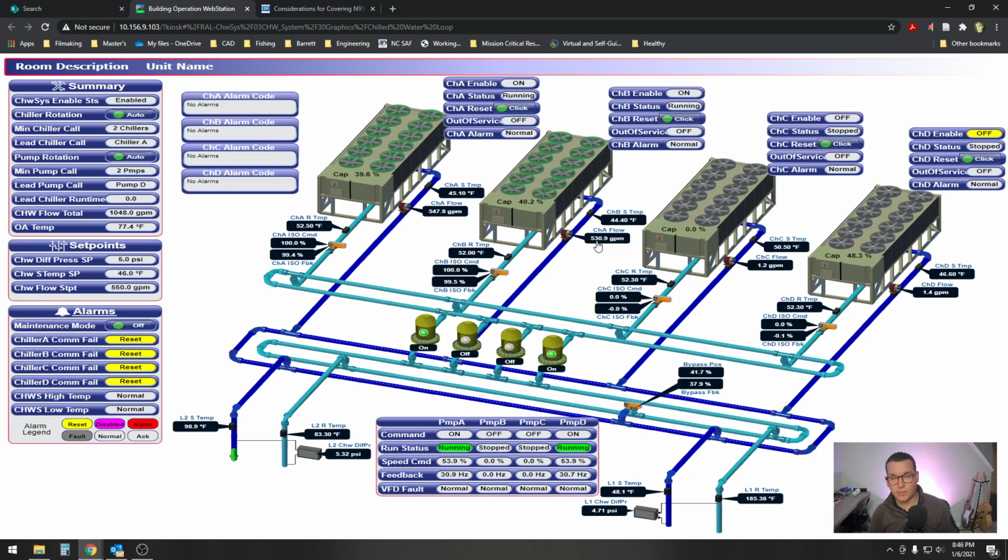So as we watch it, the pumps are varying in speed, which is why these flows are going all over the place. But we can see that it's a little bit low, so the bypass valve is going to be relatively static. But as those flows start increasing, this bypass valve closes. We just saw it happen here, just a little bit.